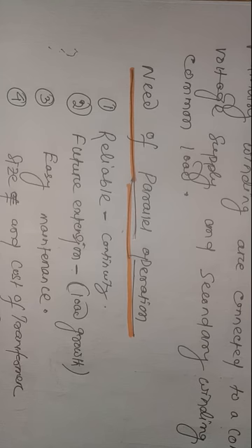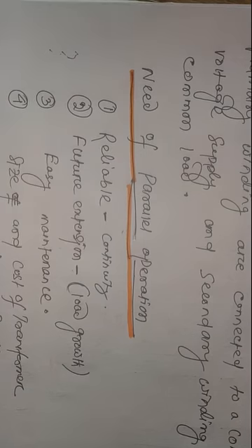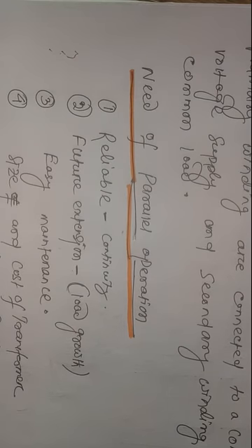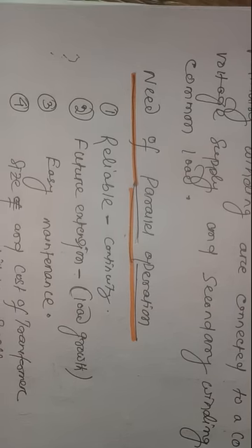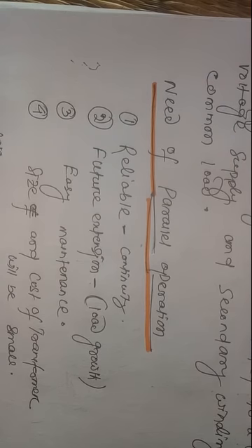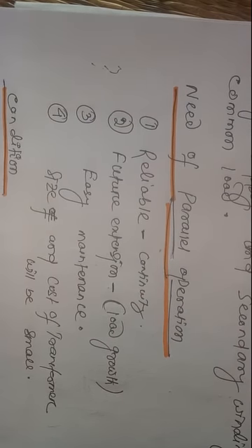So future extension is possible in this case. The third one is ease of maintenance. This is the same as reliability. If a fault occurs, we can shift the load to the other transformer, and then the faulty part can be easily maintained. Then the size and cost of the transformers will be small, because the transformer is divided. Instead of using a large transformer having large capacity, we can divide the load among different transformers, so the size as well as the cost of the transformer can be reduced.